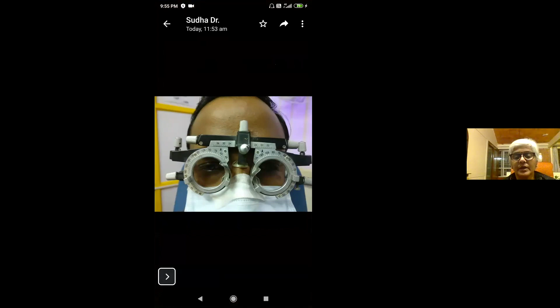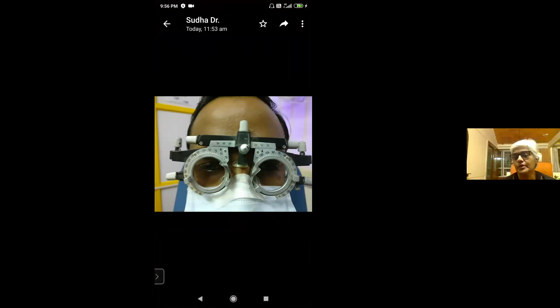You can even get a measure of PD, which may not be so important for LASIK, but the older trial frames are there, which I have also shown in that slide. Especially if that side screw becomes loose, then they are all over the place, and many times you're forced to hold it against the forehead and balance it before you can stabilize it well enough to get a proper binocular reading. Otherwise, they keep on saying that it is double, one is above, one is below. Those kinds of things you have to hear from the patients. So the trial frame being stabilized properly on the face, aligned correctly, is very important, especially in the higher powers.